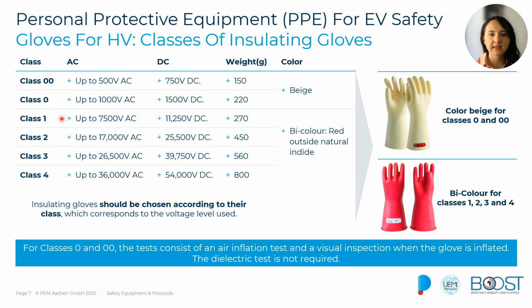If you are dealing with class 0 or class 00 gloves, in these cases we have to do a primary visual inspection of the gloves, and usually we also have to do the air inflation test. That means to inflate the glove and see that there are no air leakages and that it remains in good condition. If we have class 1, 2, 3, or 4 gloves, in those cases, usually we have to do regular dielectric testing, and it is mandatory in many standards. So often every 6 months we have to be sure that the gloves are in good condition after doing the dielectric test.